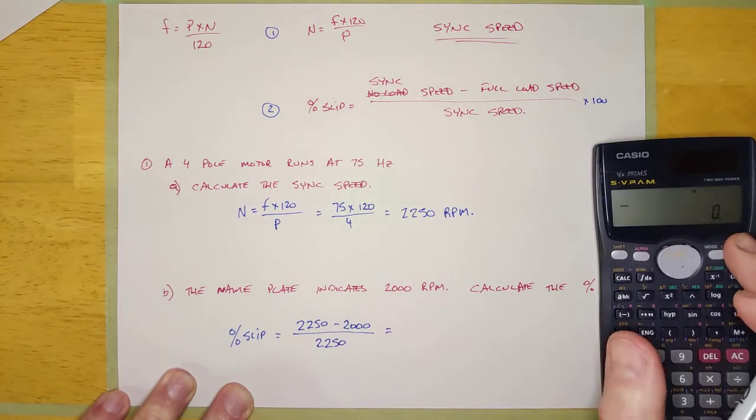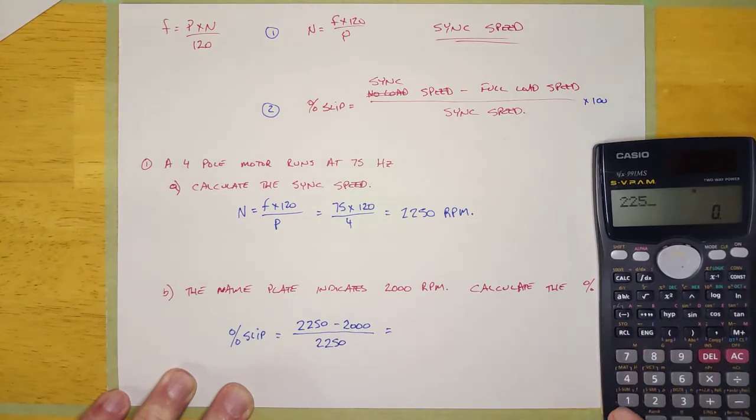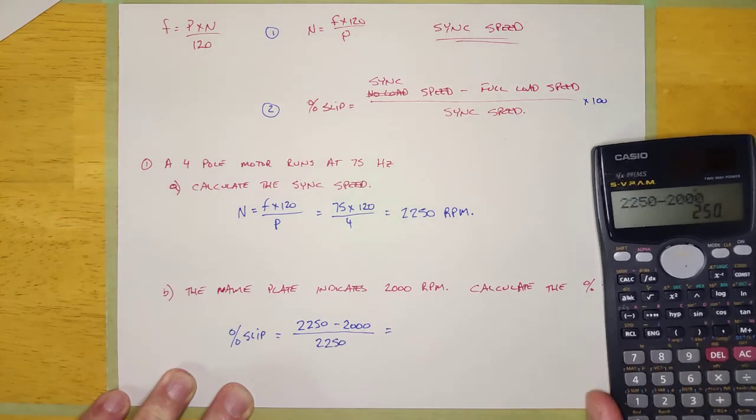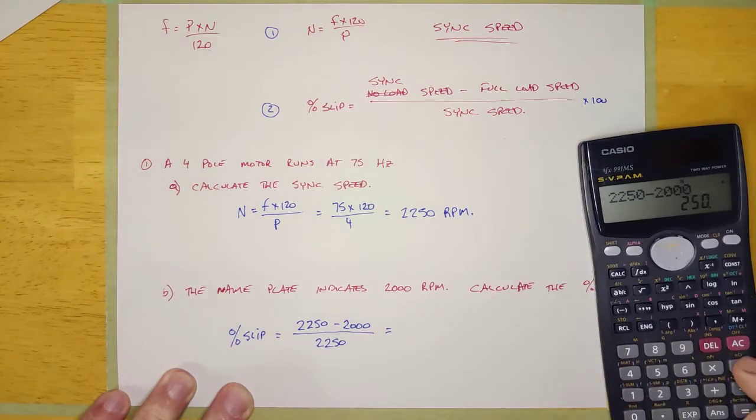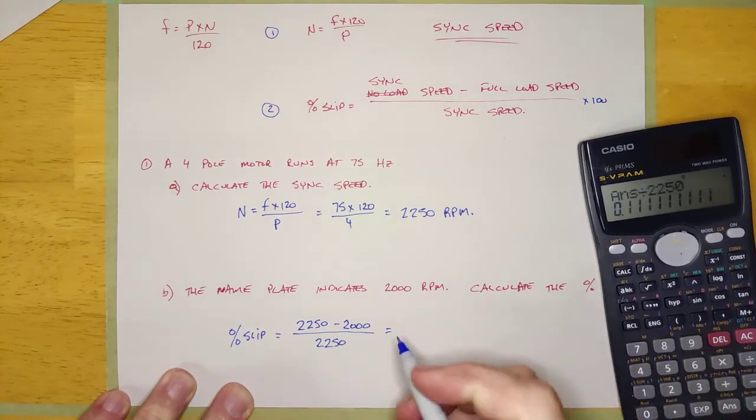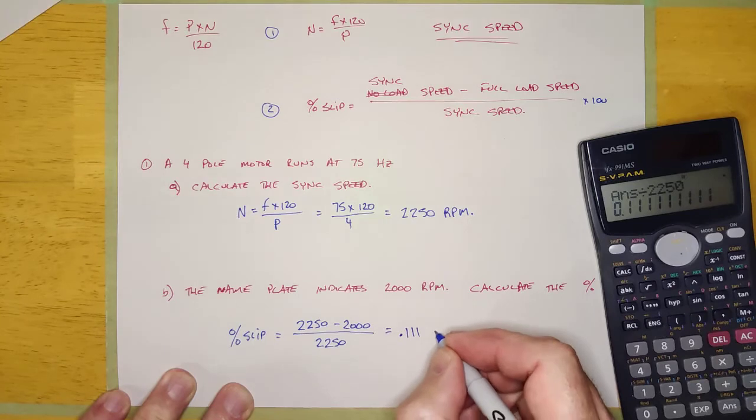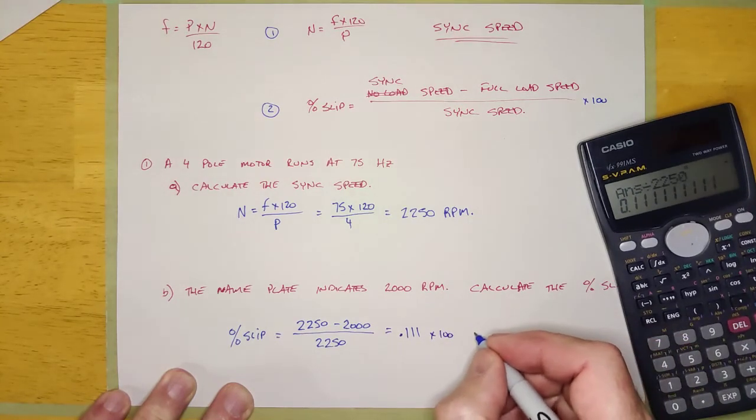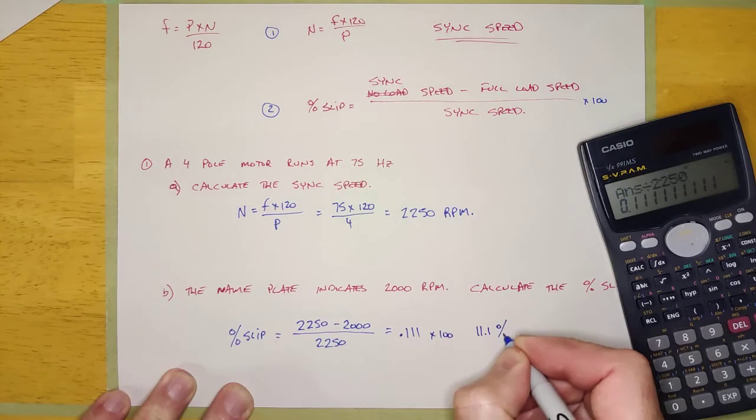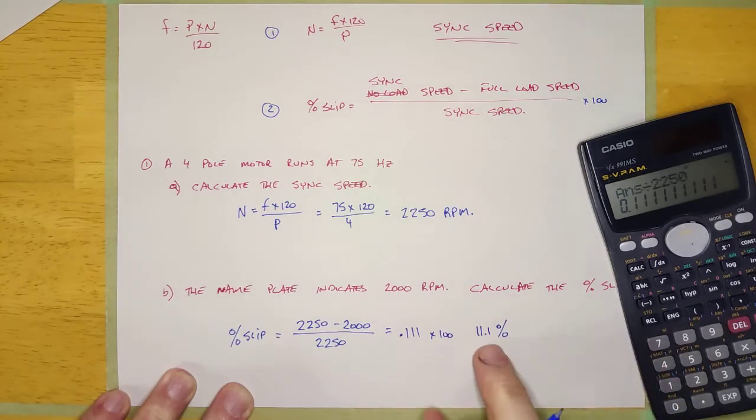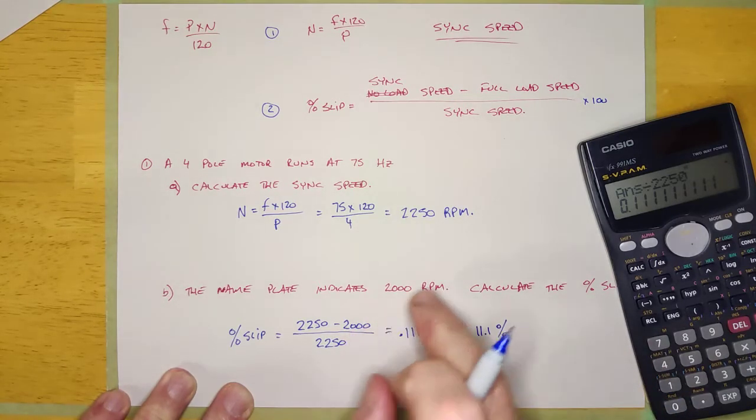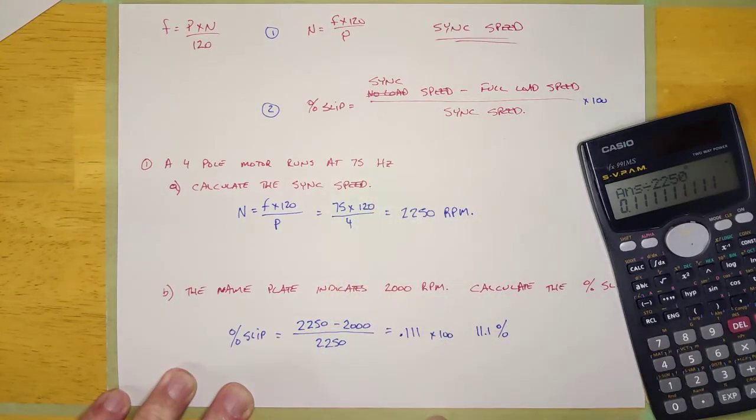And so no big deal. So 2250 minus 2000 equals, that's the 250 RPM it's slipping, and then we're going to divide it by 2250. And we're going to find out that it's 0.111, and then we're going to times it by 100 to get it in a percent, and so it's going to be 11.1%. And that is the percent slip of this particular motor.